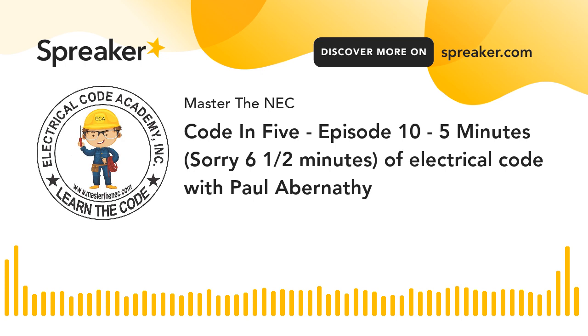Lastly, we're talking about motors. Now, if you're dealing with a design B, C, or D motor, then it says the conductors having an insulation rating of 75 degrees C or higher shall be permitted to be used. But you've got to remember, even if you use those, you can't exceed the ampacity value under the 75 degrees C column of 310.16. So it's going to allow you to use an insulation that's rated higher than the 60 degree, because those terminals for motors on a B, C, and D design typically are rated 75 degrees C.